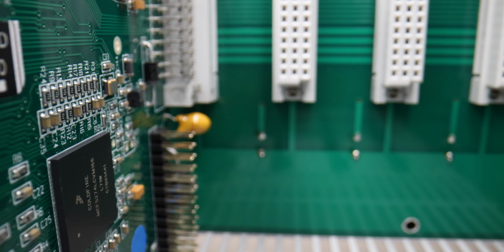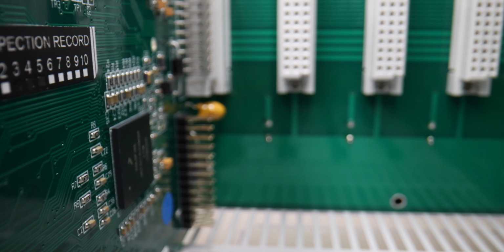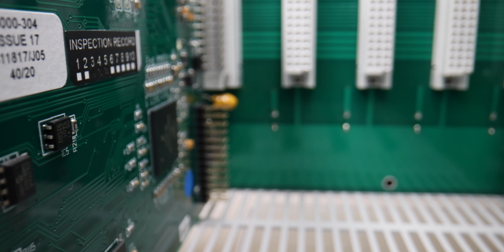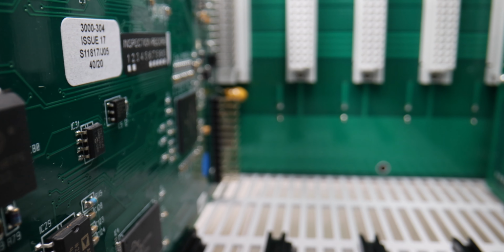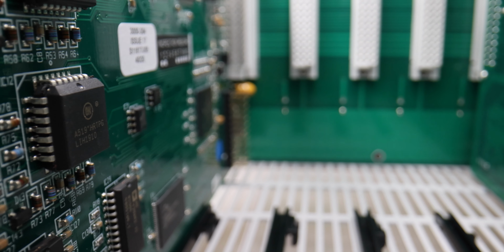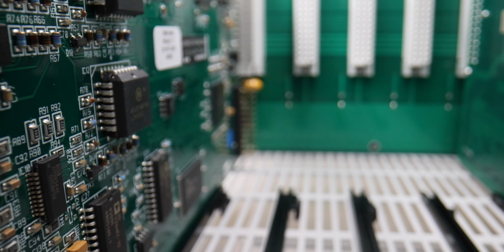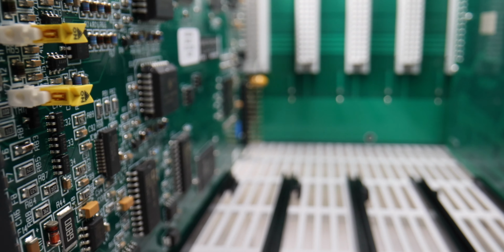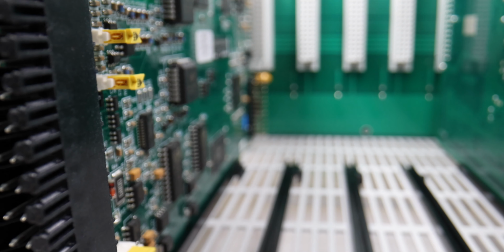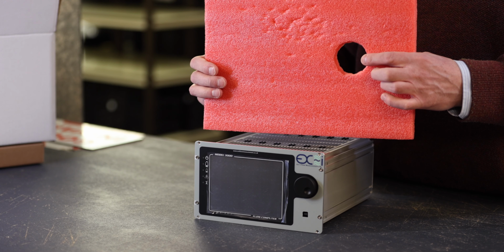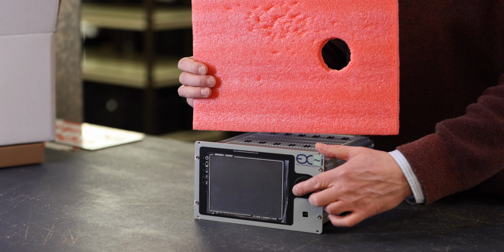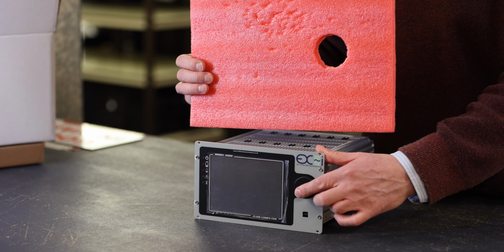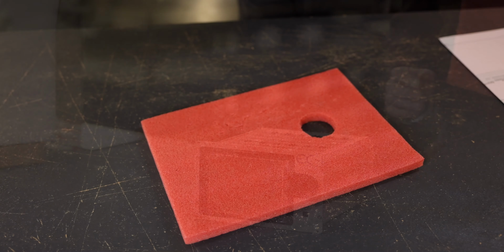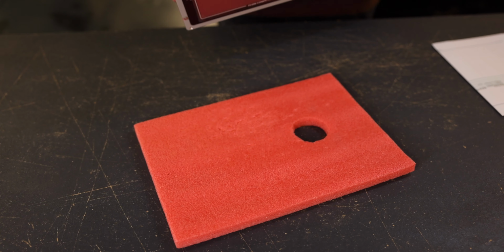The backup battery is isolated using an insulation tab to prevent the battery discharging during transportation and storage. During installation to a cabinet or commissioning, the rear panel will need to be removed to remove the insulating tab from the auxiliary board for the backup battery to work. Before removing the rear panel, care needs to be taken to protect the rotary control, as excess force will damage the push button. A piece of foam or even edge of the bench will be sufficient.